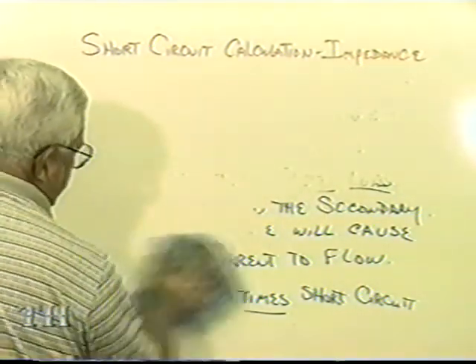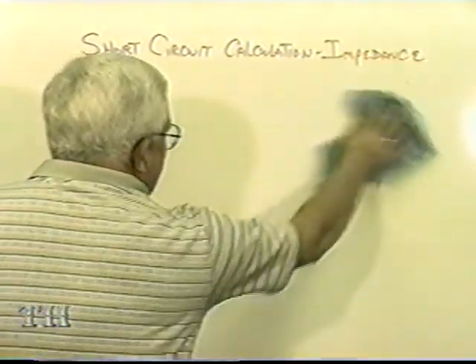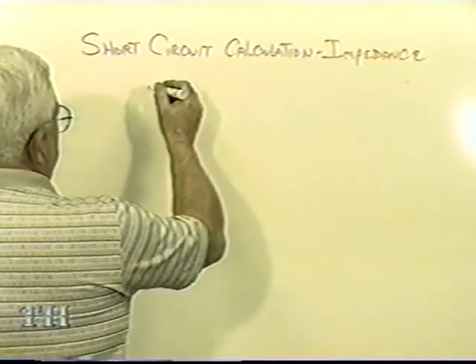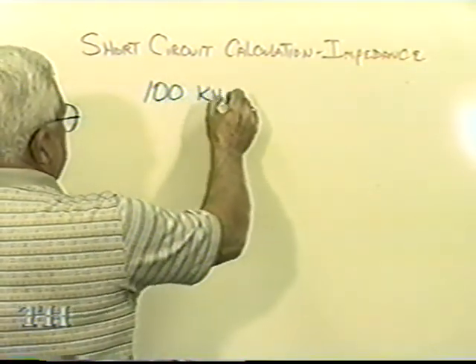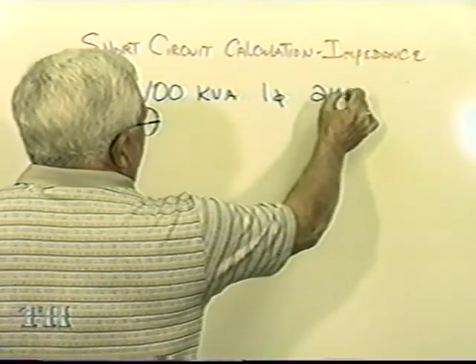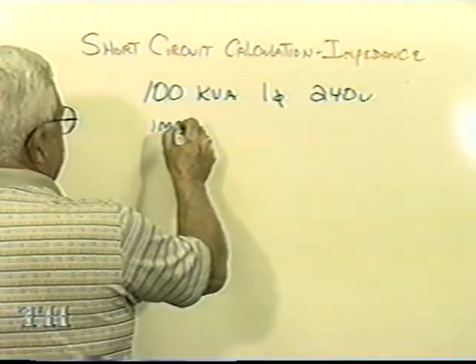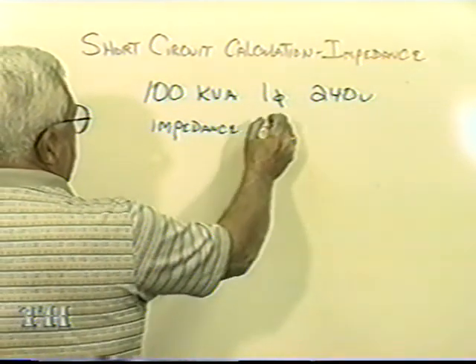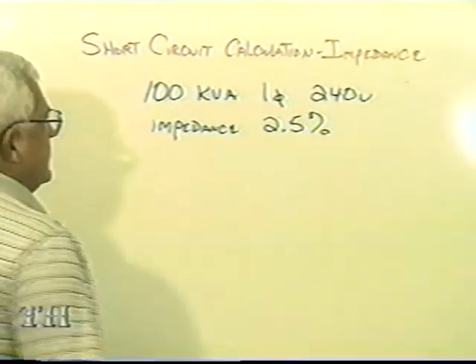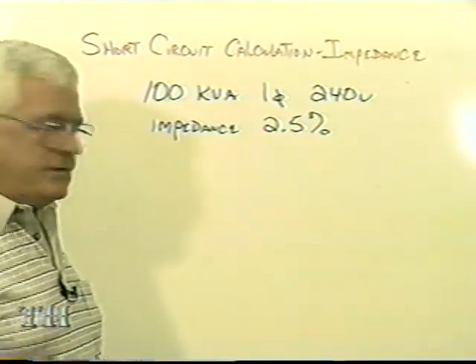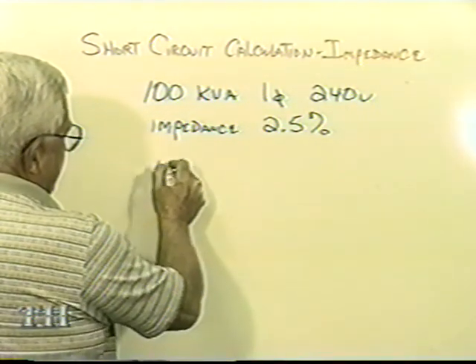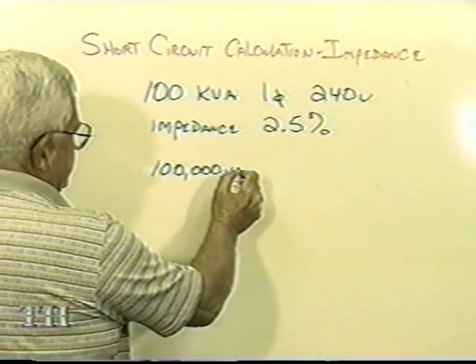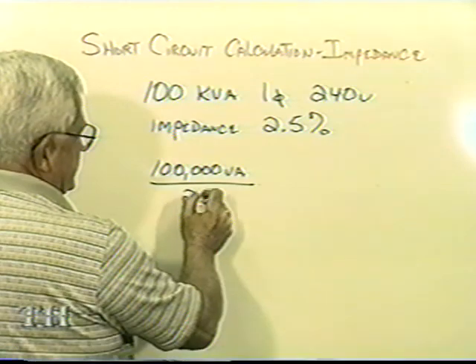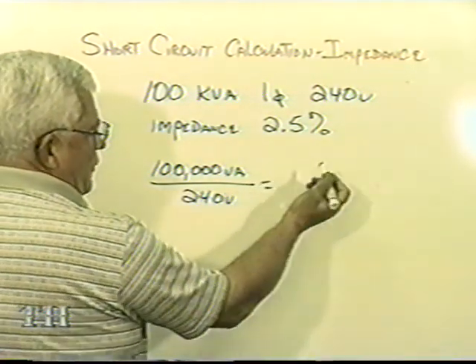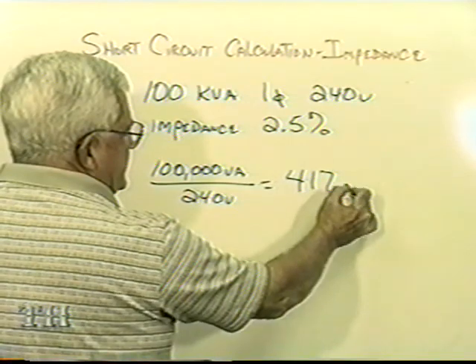Let me clear this and I'll give you an example. Let's say I got a 100 kVA single phase, 240 volts, and let's give it an impedance. It'll be on the nameplate of 2.5%. Now what you want to do, you want to find the rated current first. Well, if I would take the 100 kVA, that's 100,000 volt amps. Divide that by the voltage, single phase at 240 volts. Round it up, you should be looking at about 417 amps.